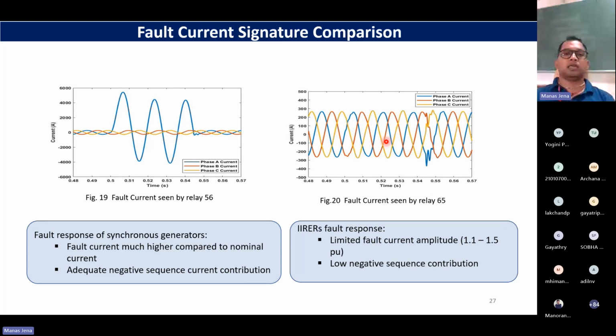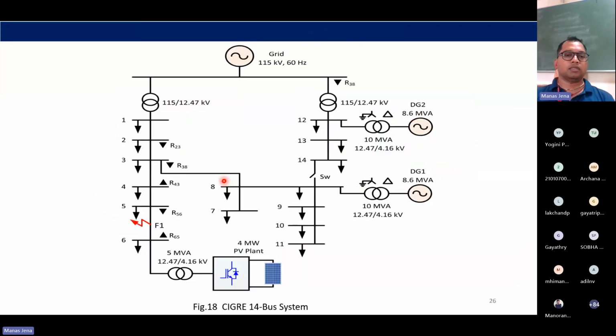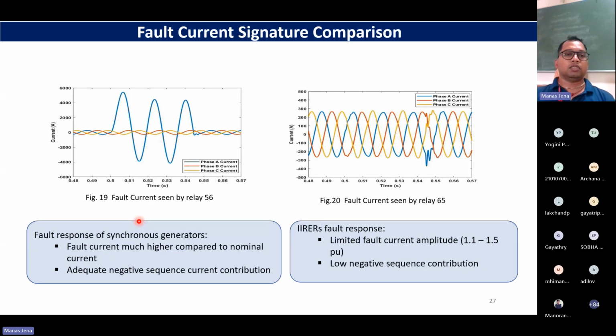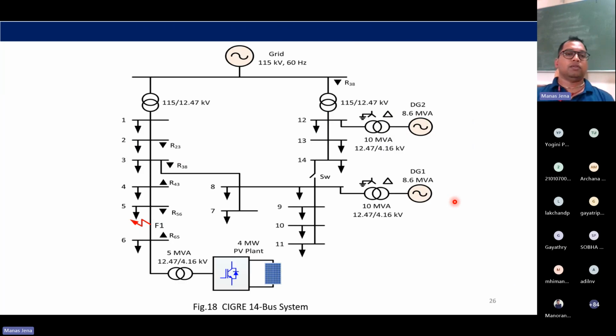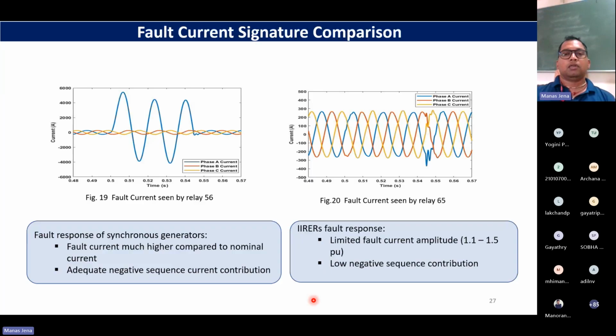So, as I was telling in words, this is something you can see visually. Look at the fault current seen by the relay R56, which I mentioned is seeing what the conventional grid is feeding. So, this is the signature we expect, right: very high fault current and a decaying DC component. This is what we expect for the conventional system. Whereas R65, the relay sitting here, which is only seeing the response coming from the inverter, sees hardly any changes, actually hardly any changes.